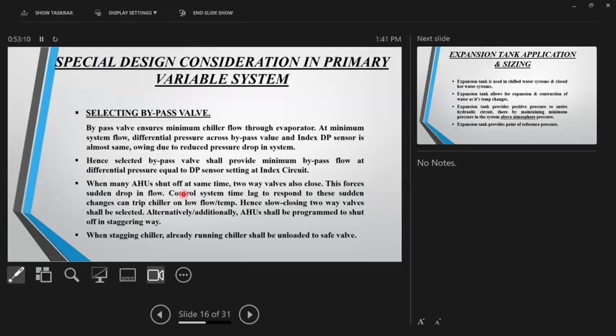So usually for a primary variable system, you should not close all the AHUs at the same time. You should have some schedule: out of 100 AHUs, probably 25 AHUs you can switch off now, the next 25 probably 2 minutes later, and the next 25 maybe after 5 minutes, so that the impact of flow reduction is understood by the control system. It's not a sudden jerk.